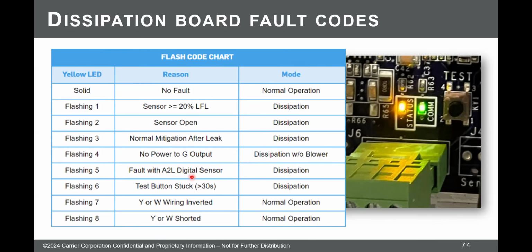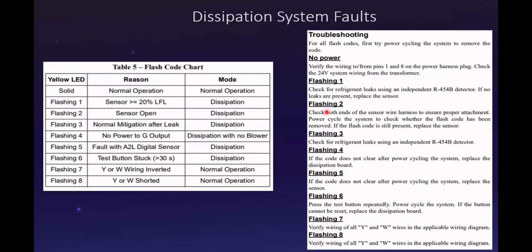The sensor, if it's not working, it can send a message to the board saying, hey, I don't feel good today. I got the flu, bro. I'm not coming in. Like, I'm done. Like, I'm baked. So it could send a message like that. And there's also a few wiring errors that could generate a blinking light. But basically, you're counting the blinking light, reading the book to see what it says about that, right? So, 3 flashes. Check for refrigerant leak, with a refrigerant detector, right?